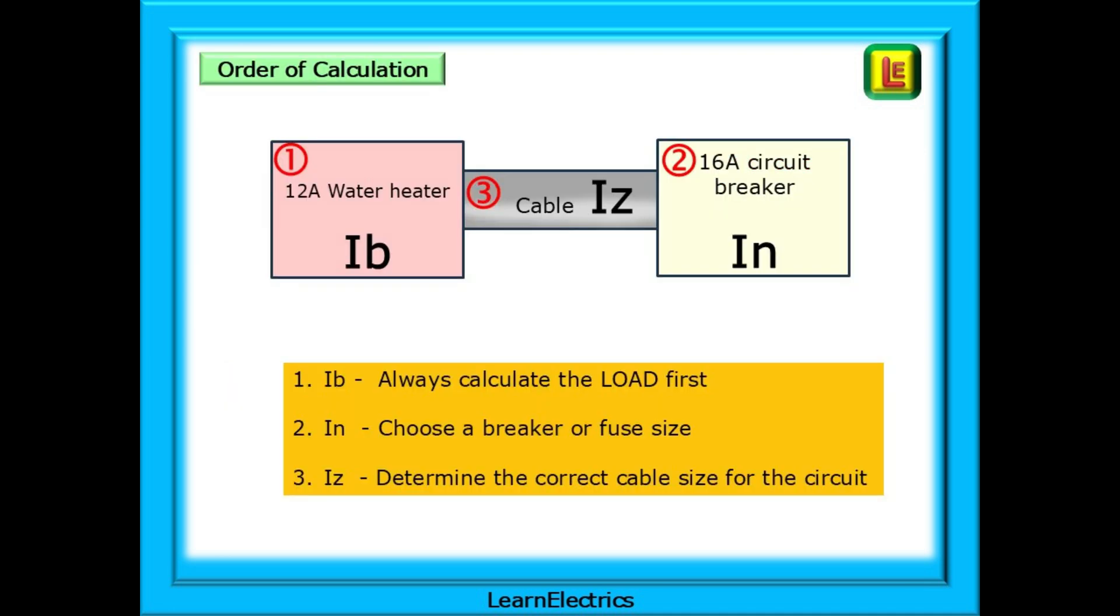There is a specific order of calculation that must be followed. First is IB. We always calculate the load first. Then IN. So that we choose the correct breaker or fuse size. And finally, IZ. We can determine the correct cable size for the circuit.